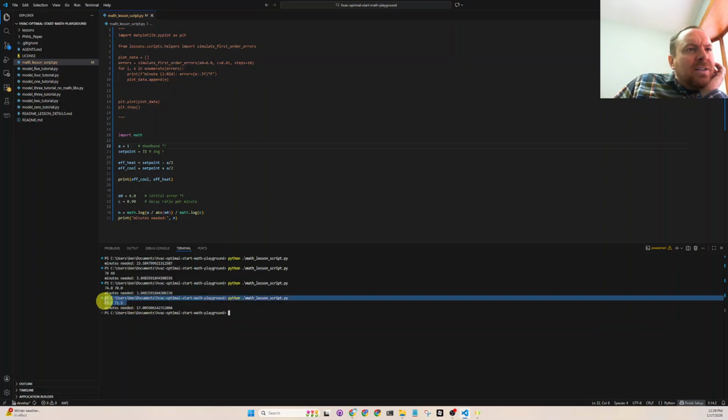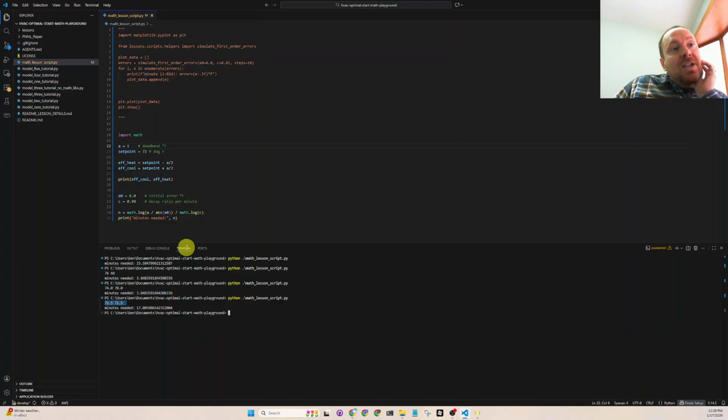Our deadband is a lot smaller. So with a 1-degree deadband, we only get half a degree up and down. That would be a really small deadband, which can make some equipment overshoot and undershoot.